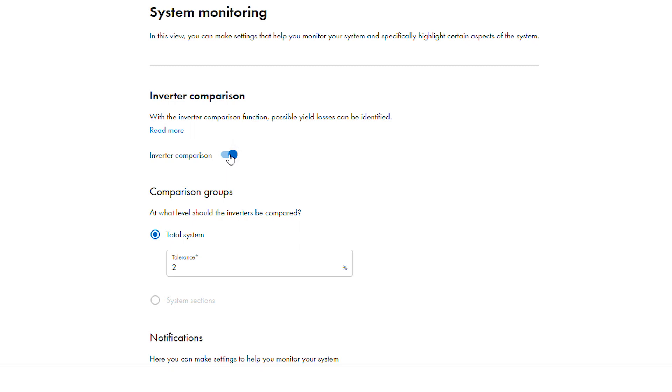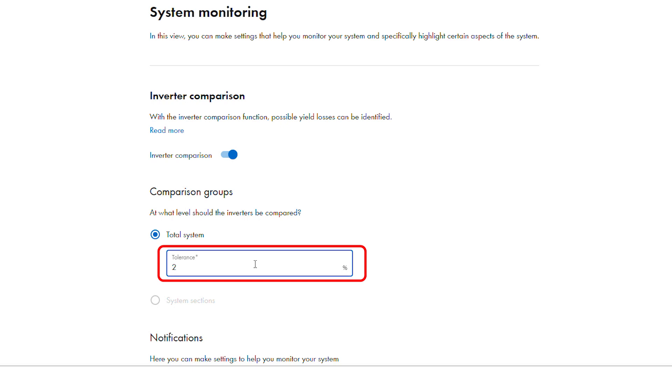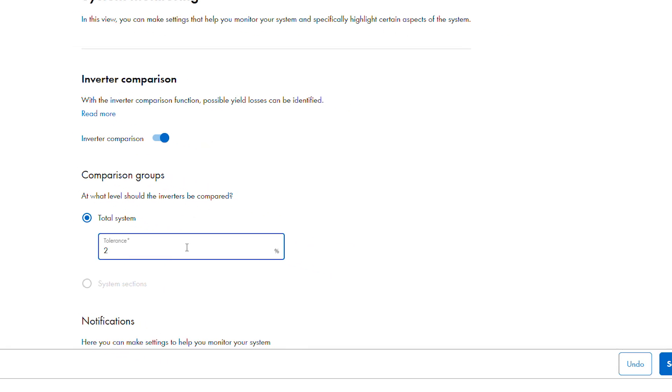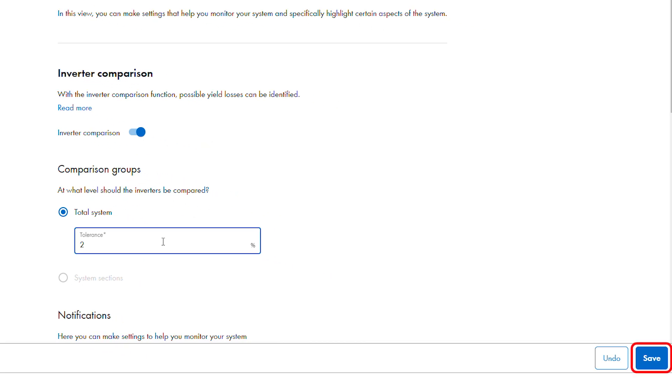The tolerance can be adjusted from 20% up or down. This tolerance refers to the specific yield of any one of the inverters compared to the mean of all the other inverters. To change the tolerance, adjust the value in the box and then click save at the bottom right of the window to store the change.